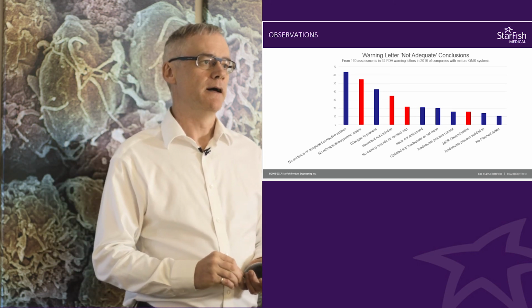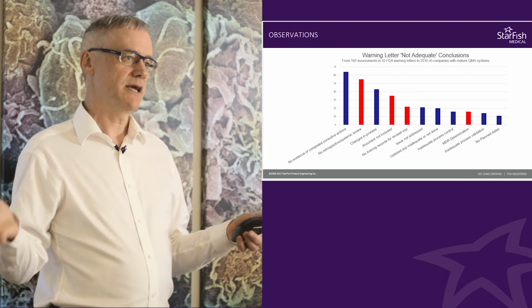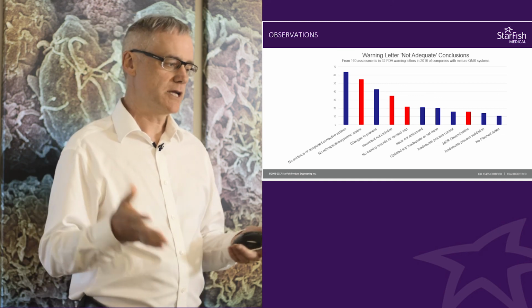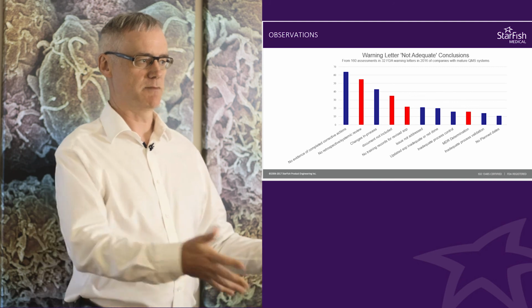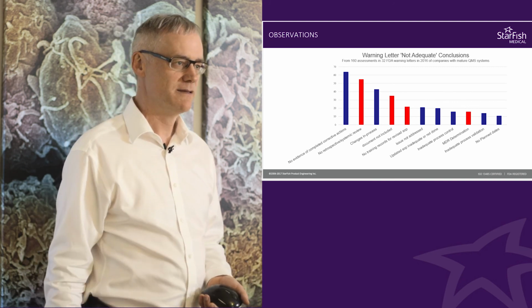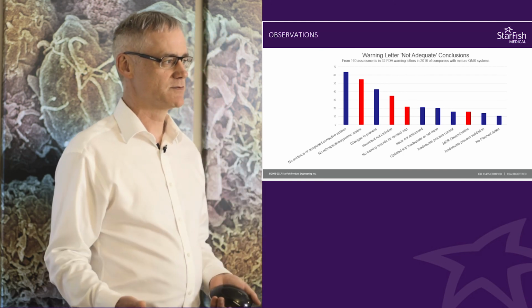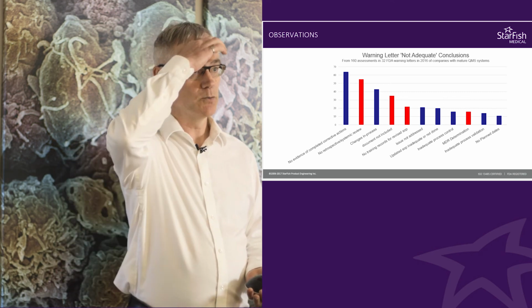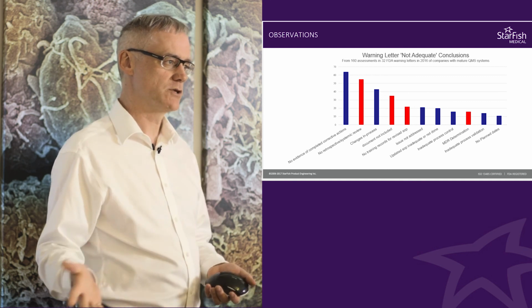In about a third of the cases where the 483 turned into a warning letter, the document was not included. They didn't actually submit the revised document, and the FDA said, well, it's nice that you made this change, but you didn't send us the document. What a dumb reason to get a warning letter. That's very easy to have as an oversight. And then the next one was no training records, so you didn't actually show that your revision was implemented.